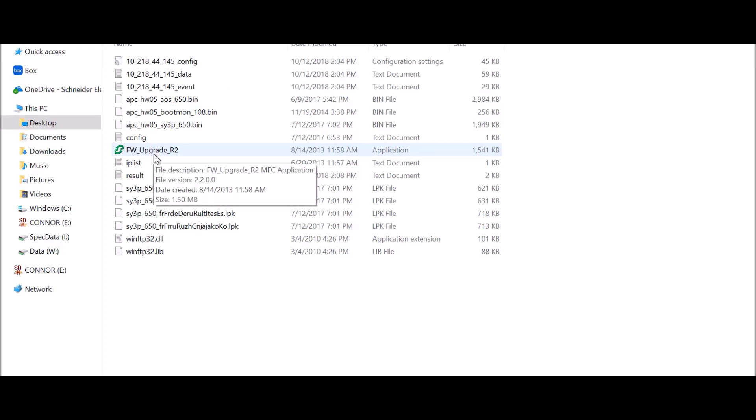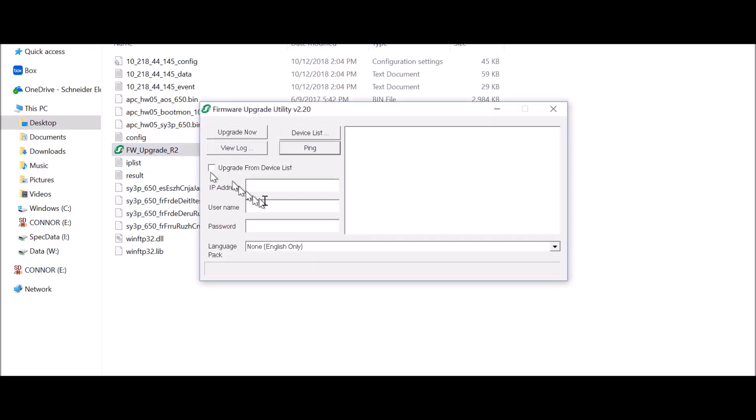Locate and click the Firmware Upgrade Utility application. Enter the IP address of the Network Management Card 2 whose firmware you would like to upgrade.